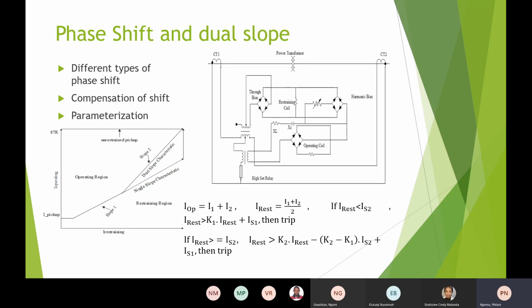Parameterization, that is one I will also go for training on, to test the relay and visit the SEL company. As the presentation shows, the harmonic restraining diagram with the harmonic bias, through bias, restraining coils and operating coils, and also the dual slope showing the unrestrained pickup, operating condition, and the restraining region.